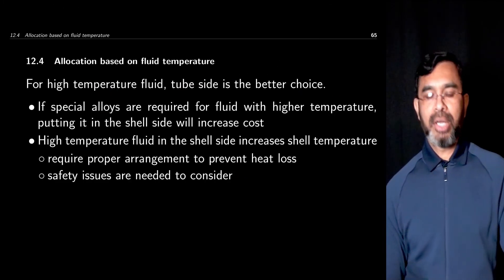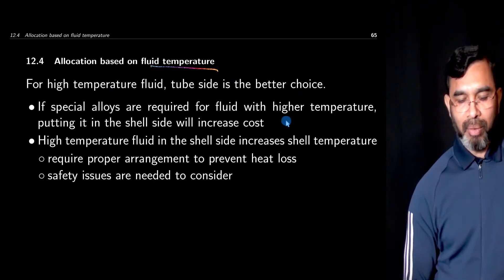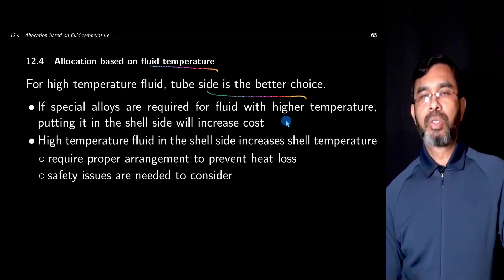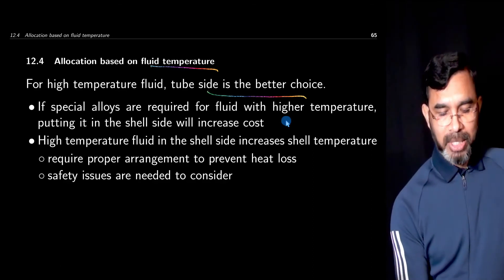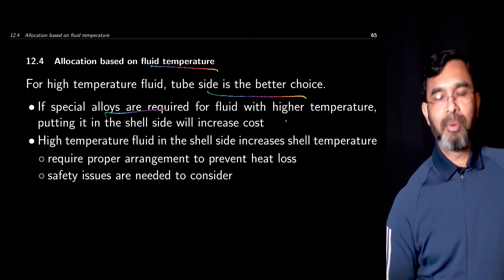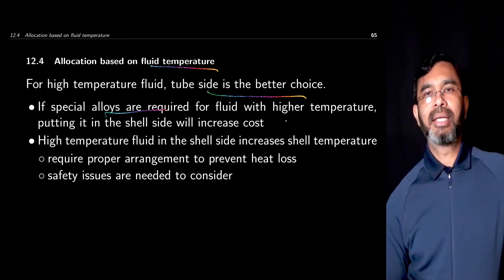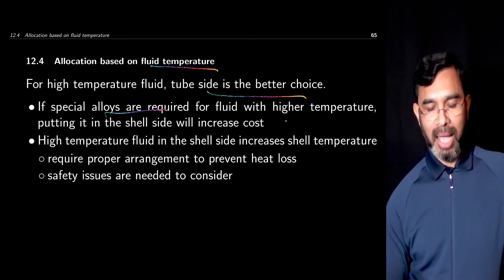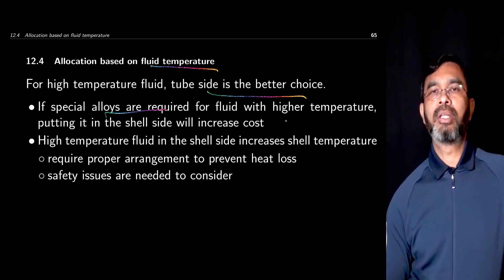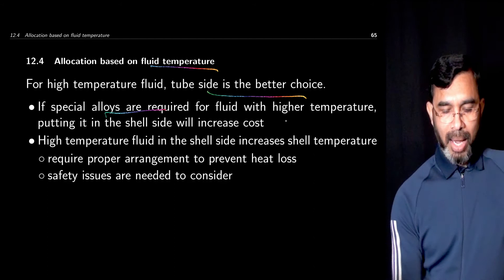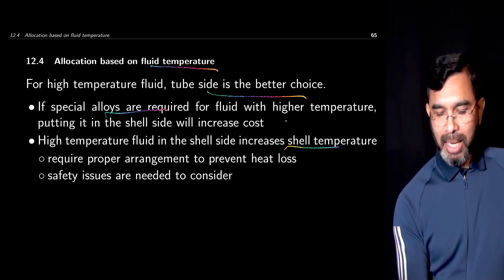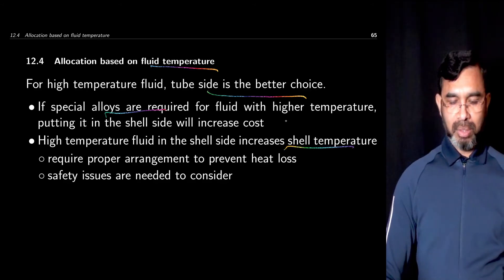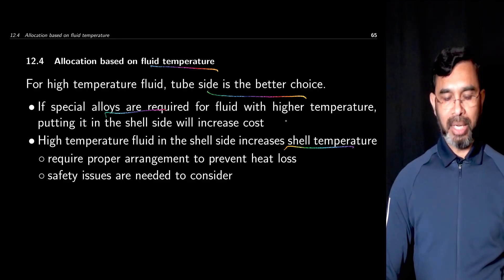When considering fluid temperature, for high temperature fluid the tube side is the better choice. If a special alloy is needed due to high temperature and you put this fluid on the shell side, all materials must be constructed using that special alloy. However, if you put it on the tube side, only the tubes need to be constructed with it. Also, high temperature fluid on the shell side increases the shell temperature and causes heat loss from the heat exchanger.